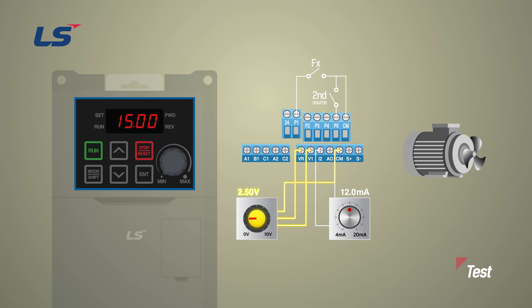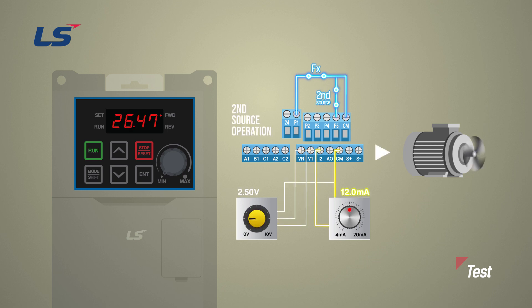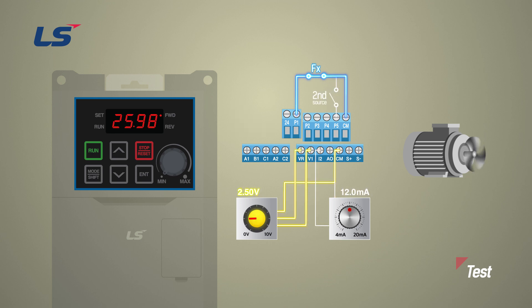Turn terminal P1 on to perform the operation. Terminal P5 is off, so you drive at the frequency of the basic operation, 15 hertz. Switch terminal P5 on — frequency command has changed to current and operating speed will be changed to 30 hertz. Turn terminal P5 off again and speed has changed back to 15 hertz.